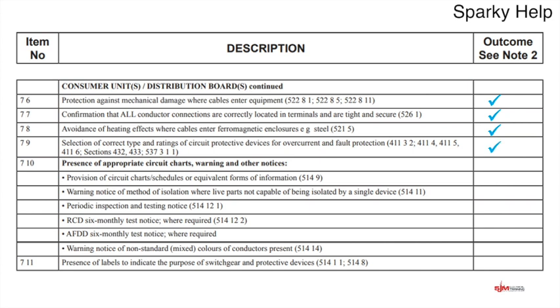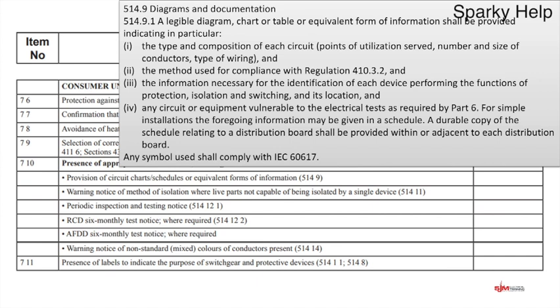The next one, presence of appropriate charts, warning notices and other notices. Hopefully fairly self-explanatory. What do the regulations require? It says a legible diagram, chart or table or equivalent form of information shall be provided indicating in particular, and then it lists 4 different things down the side there. So type and composition of circuit, points of utilisation served, number and size of conductors, type of wiring, to name but a few. And a durable copy of the schedule relating to the distribution board shall be provided within or adjacent to each distribution board.